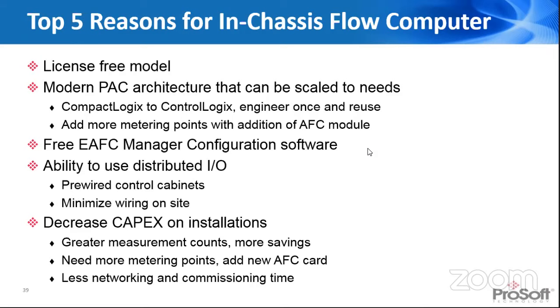The AFC Manager software, being a tool for measurement groups, is free configuration software. With the ability to use distributed I/O and place your I/O out near your separators, near your tank batteries, near your wellhead, it provides a lot of flexibility in the architecture, can decrease the amount of wiring, decrease your commissioning time, and allow these sites to get started up quicker.